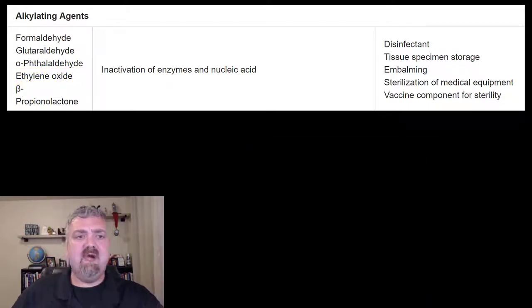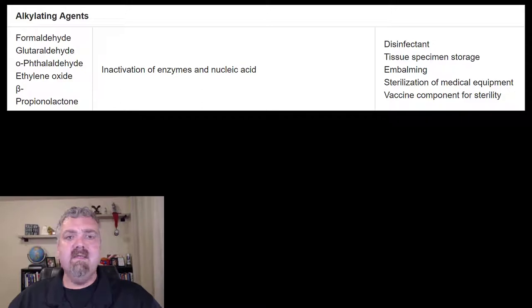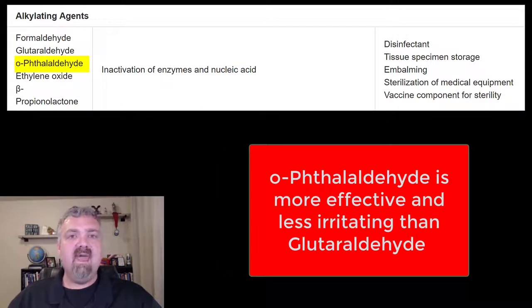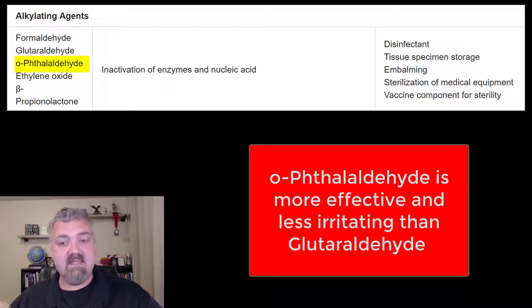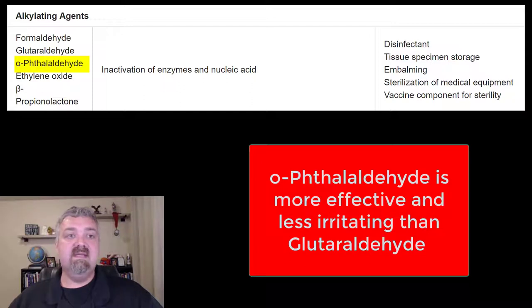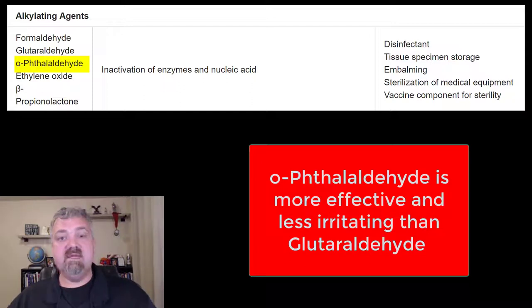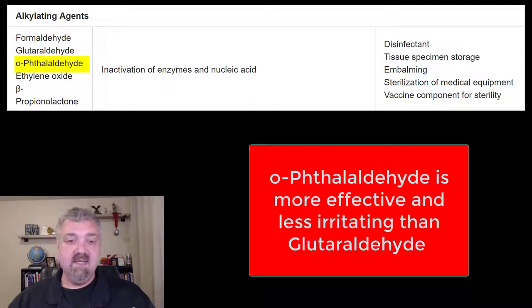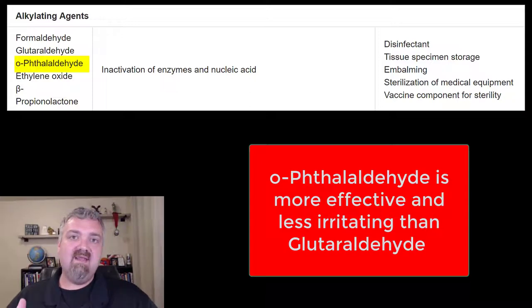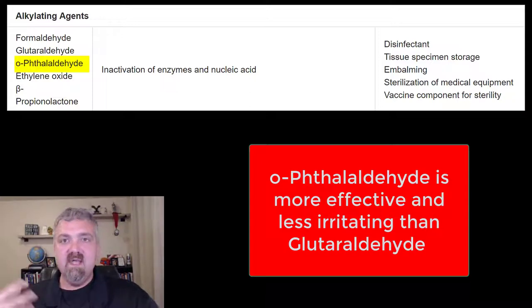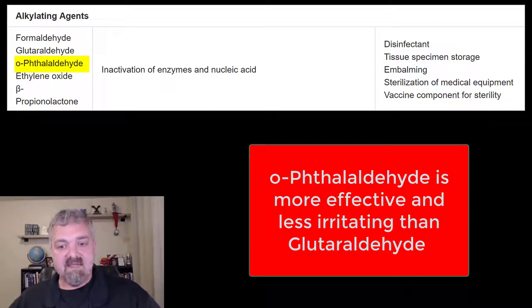A newer one — OPA, o-phthalaldehyde — is slowly replacing glutaraldehyde. You'll see this in newer formulations of Cidex, the brand name. The reason it is becoming more popular is because it's actually more effective, especially against the mycobacterium that cause tuberculosis, but is less irritating and doesn't smell as bad either. Hopefully we continue to find and replace old chemicals with ones that are more effective and less irritating.